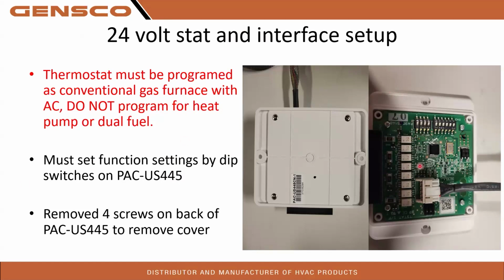If you have one of the PAC 445s, all your function settings, your economic balance point, your fan settings, all that kind of stuff is going to be done using these dip switches right here in the 445. In order to get this cover off the 445, you have to pull these 4 screws out on the back side, and then the whole front cover comes off. These dip switches need to be set with power off. So before you even power the system on, you should be setting these dip switches.